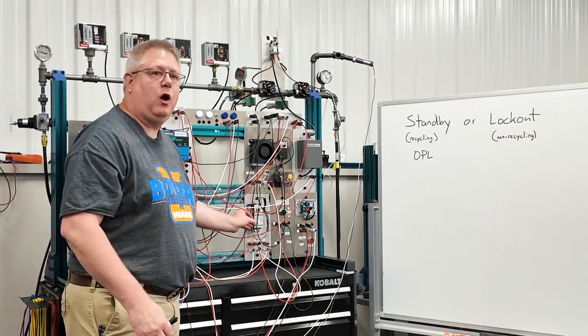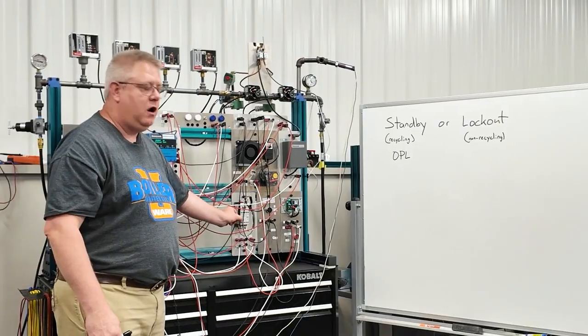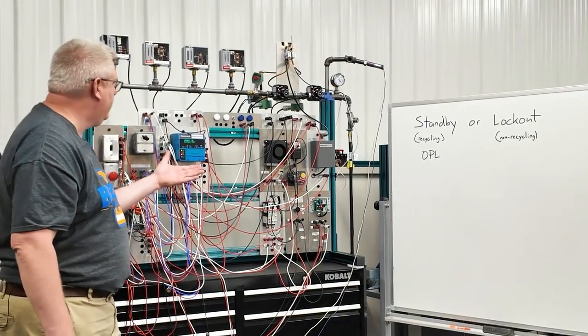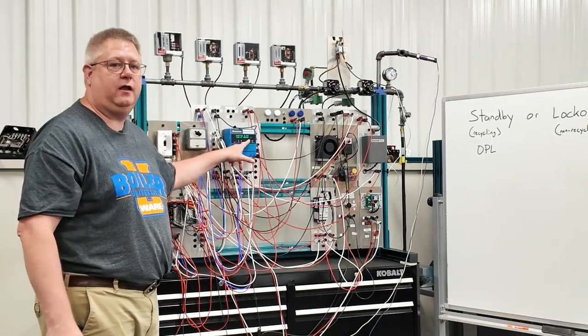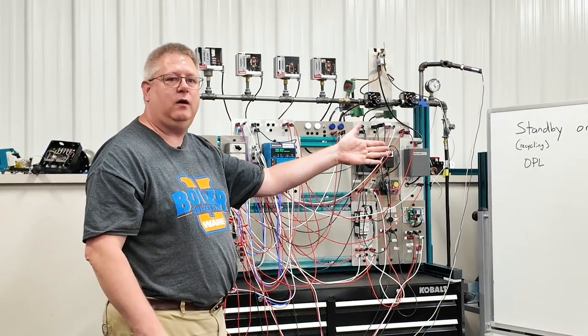If I disable my blower motor during purge, our blower motor starter interlock is going to trip us out. So we're going to get a lockout interlock. So we'll add that to our lockout list.